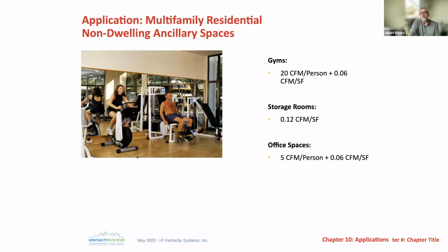So the small in-room 30 to 50 CFM devices would not be good enough for a room that has, you know, you look at the gym, it's 20 CFM per person plus 0.06 CFM per square foot, right? So we need actually a fairly large unit to be able to pull that off.